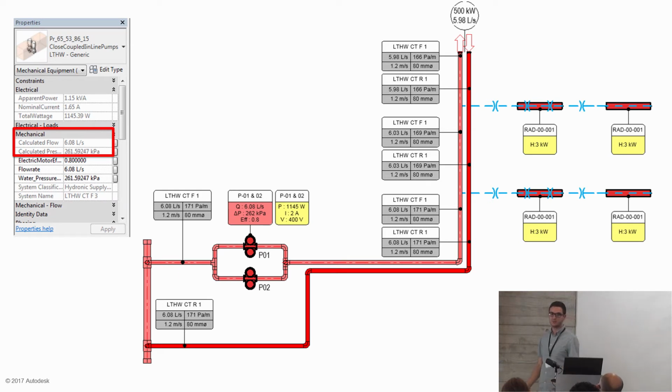We're now able to embed more analysis into our models and speed the process up. If we change stuff in the model, the calcs are automatically updated, and obviously all the scheduling's updated as well. There are a few pitfalls with this though. We found that, like in this scenario here where you've got two pumps, I've actually cheated and disconnected the secondary side.